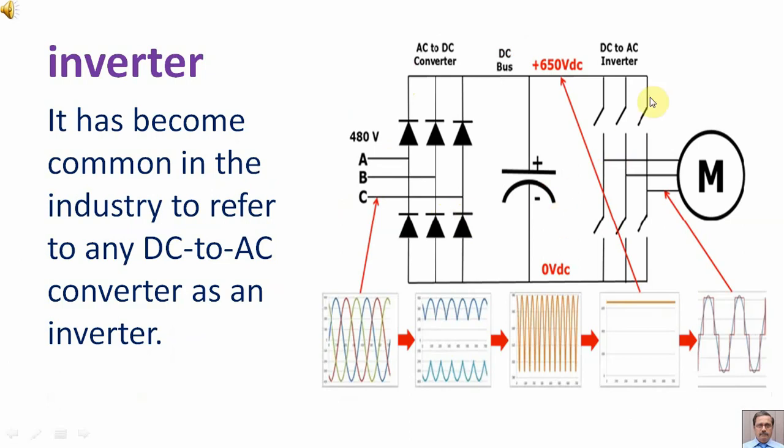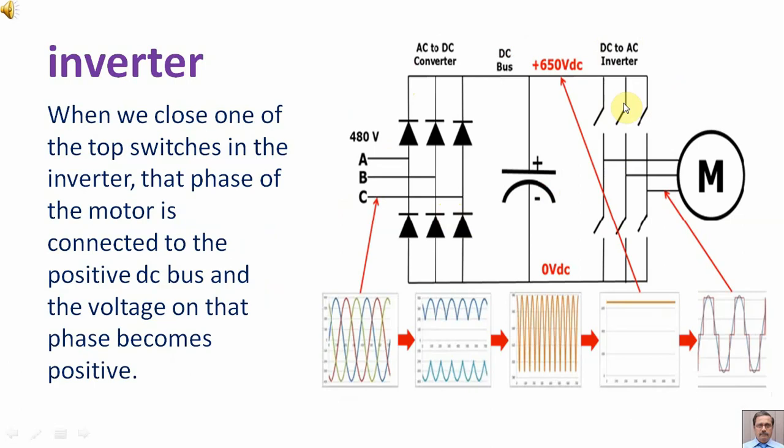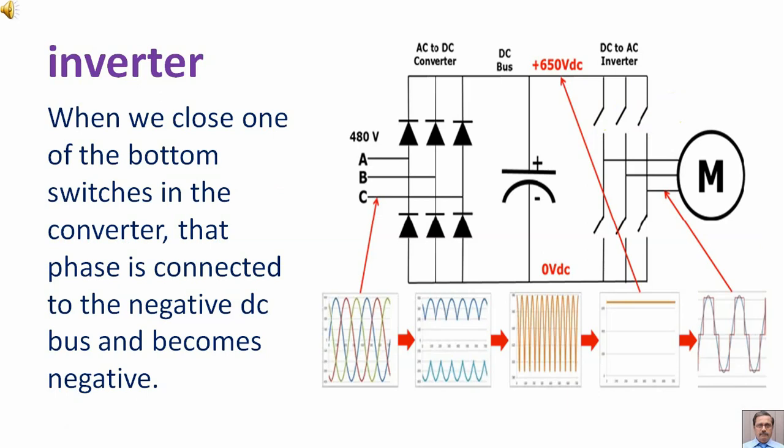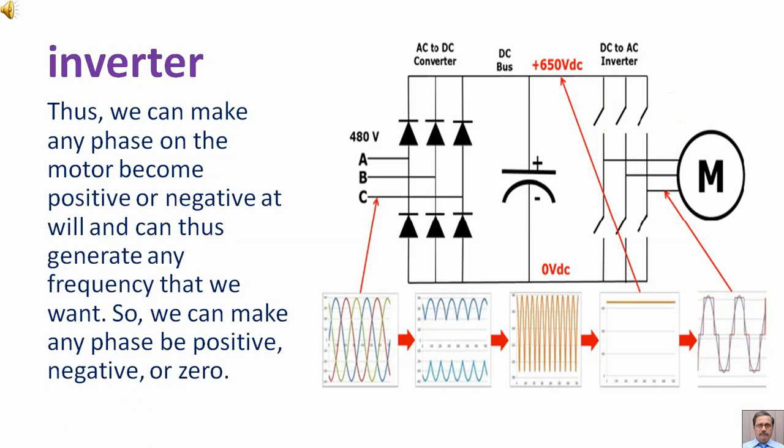Inverter. It has become common in the industry to refer to any DC to AC converter as an inverter. When we close one of the top switches in the inverter, that phase of the motor is connected to the positive DC bus and the voltage on that phase becomes positive. When we close one of the bottom switches in the converter, that phase is connected to the negative DC bus and becomes negative.